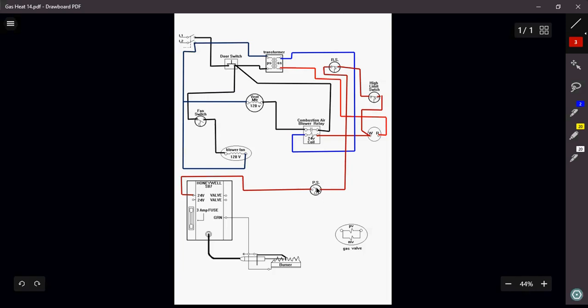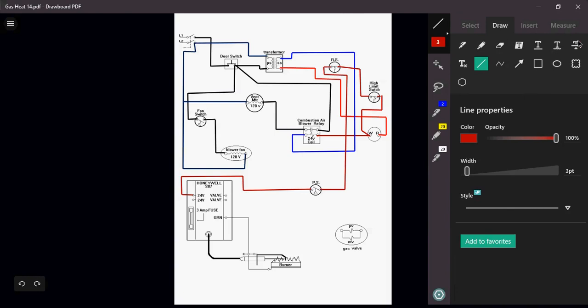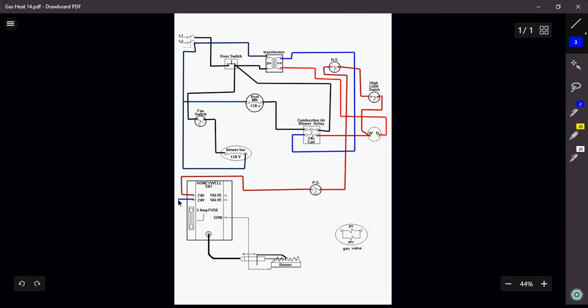Okay, so once that pressure switch closes and it proves that there is a draft and that there is a pressure difference inside my heat exchanger, it's going to close. Once it closes, I am now going to send my signal to my ignition module, and now I can begin to make my furnace operate and actually light off. So to complete that circuit, all we're going to do is come back out of my 24 volts here. This is my common. Come out, and I'm just going to connect my common. Boom. Just like that.